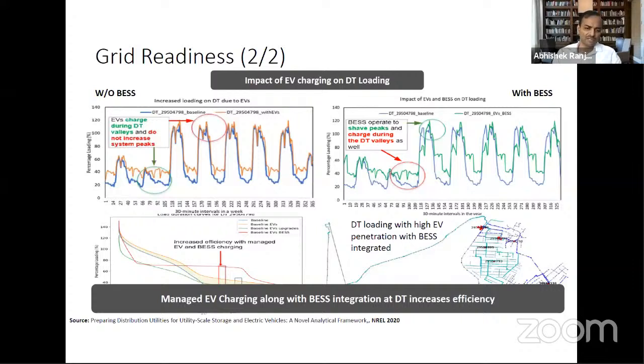On the left-hand side bottom, the red curve shows the utilization of the total DT is increased, the load duration curve and utilization pattern of the DT actually increases. On the right-hand side, DT loading with high EV penetration and BESS integrated leads to a relaxed grid without much overloading. This is as per the study done by NREL for us last year in 2020.